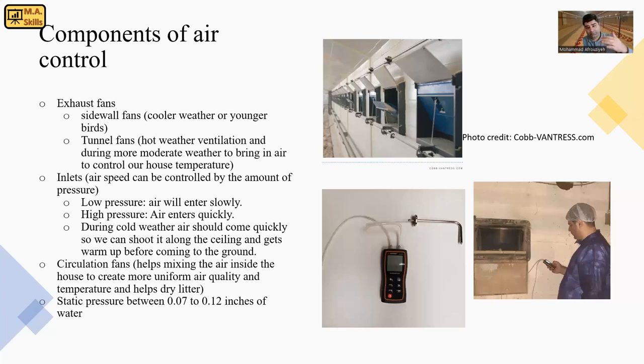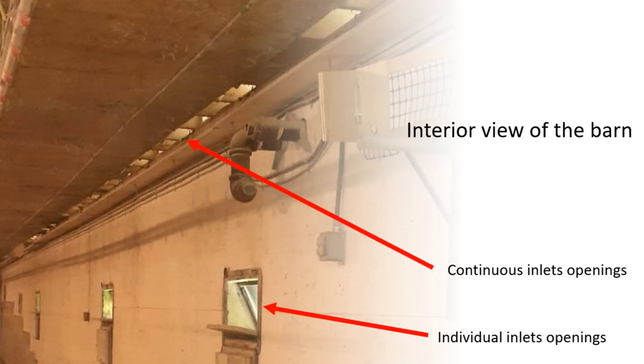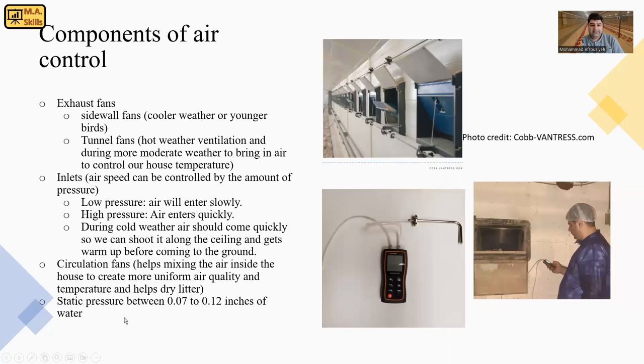Inside a cross ventilation system, we can have continuous inlets, as Tara showed in her video, and also individual inlets. For example, for older birds after the brooding phase and during summer time, we can use individual inlets. As a guideline, static pressure should be between 0.07 to 0.12 inches of water when measuring by manometer.